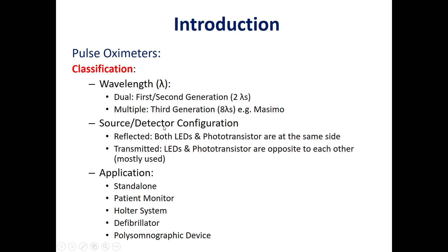Another classification of pulse oximeters is according to the position of the source and detector in the probe. We have two types: the reflected type and the transmitted type.